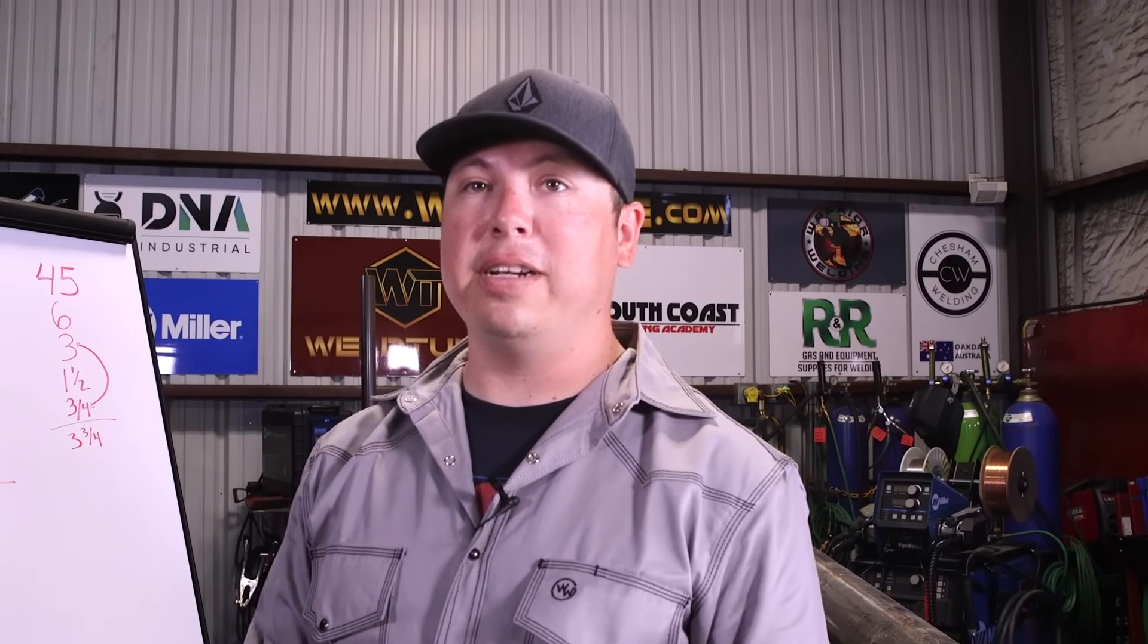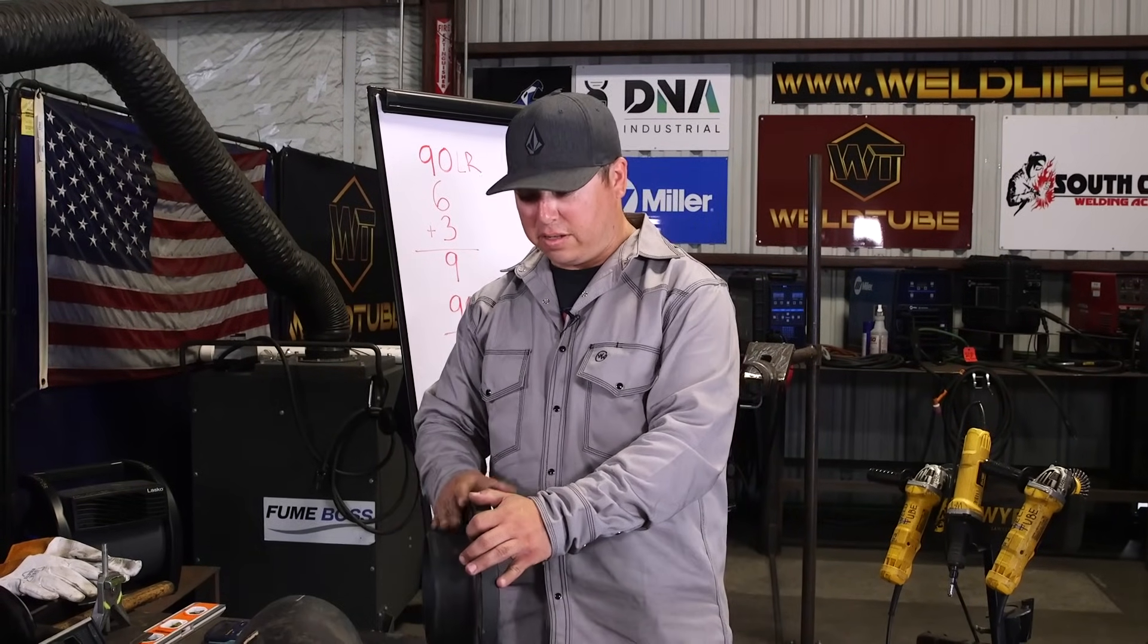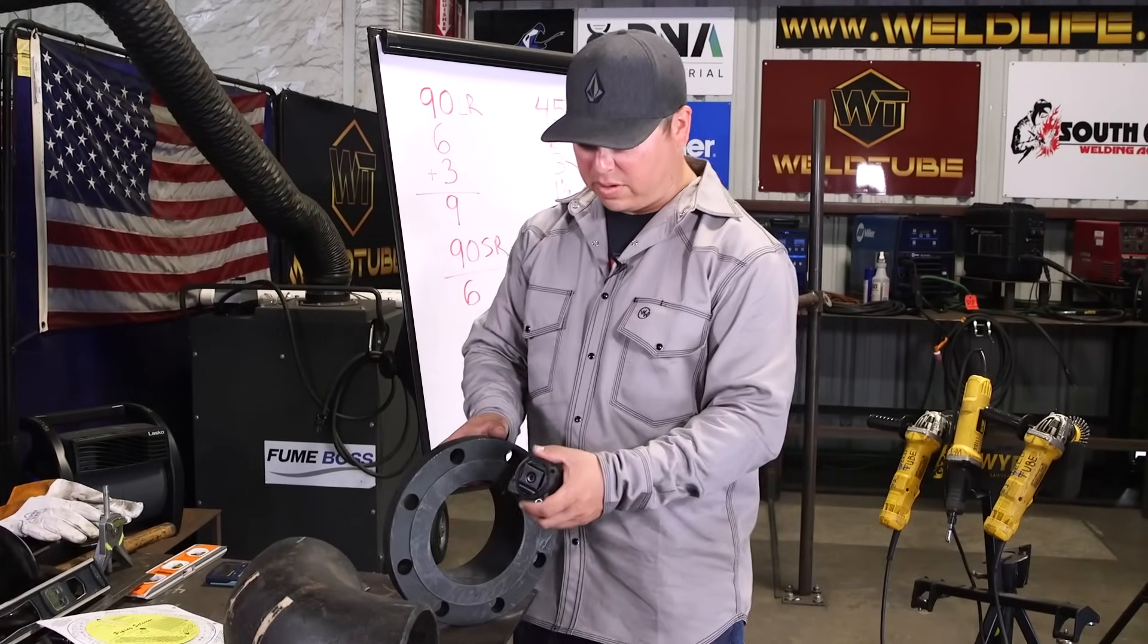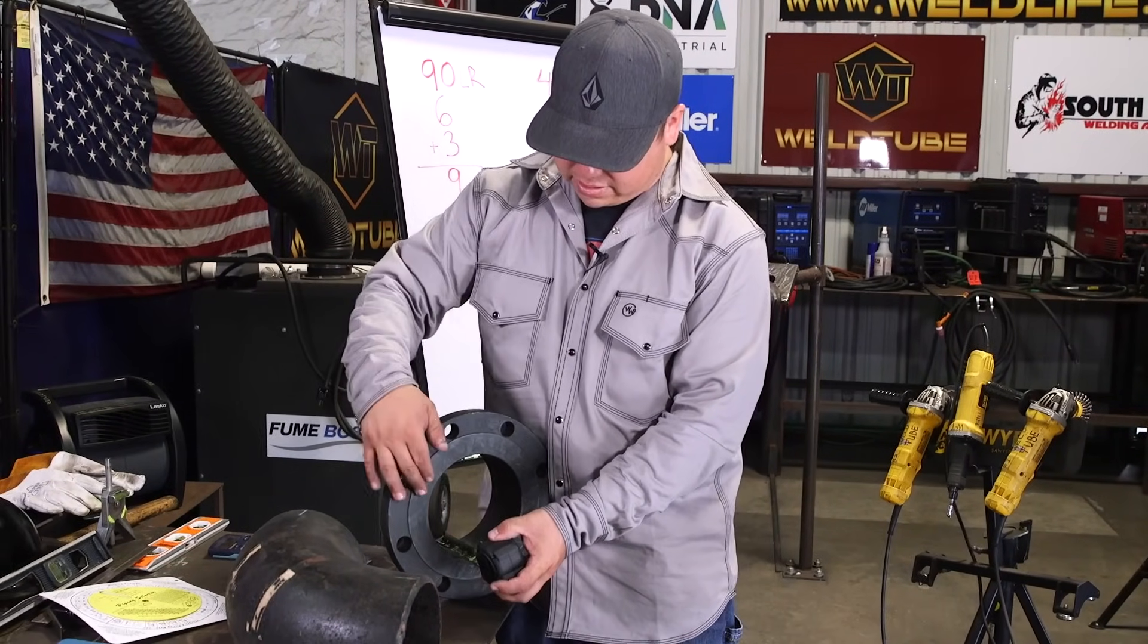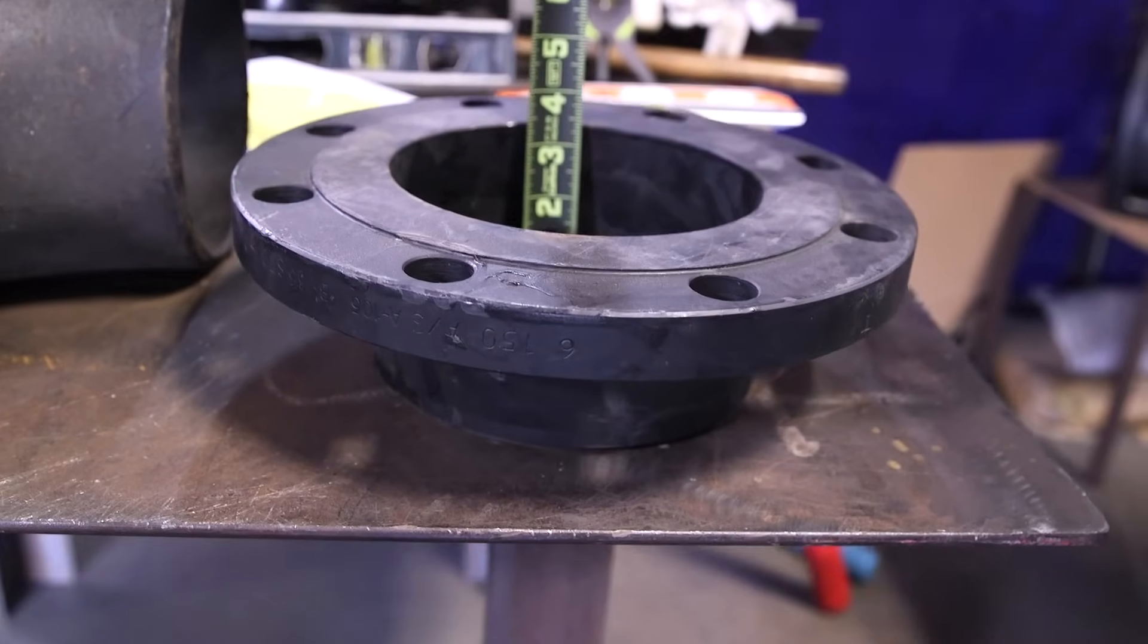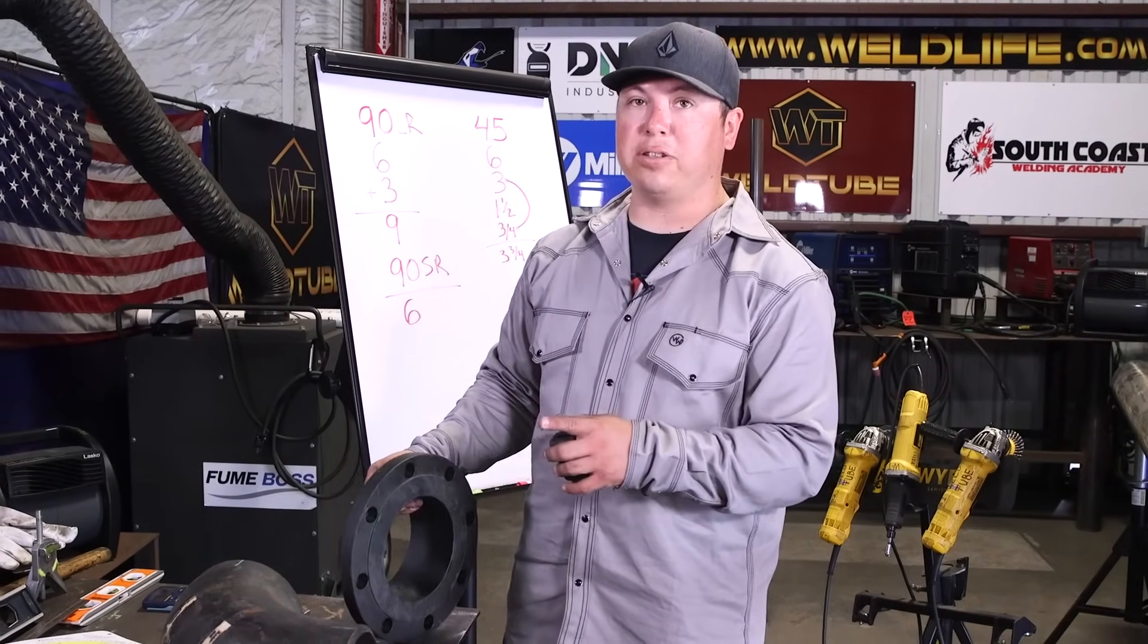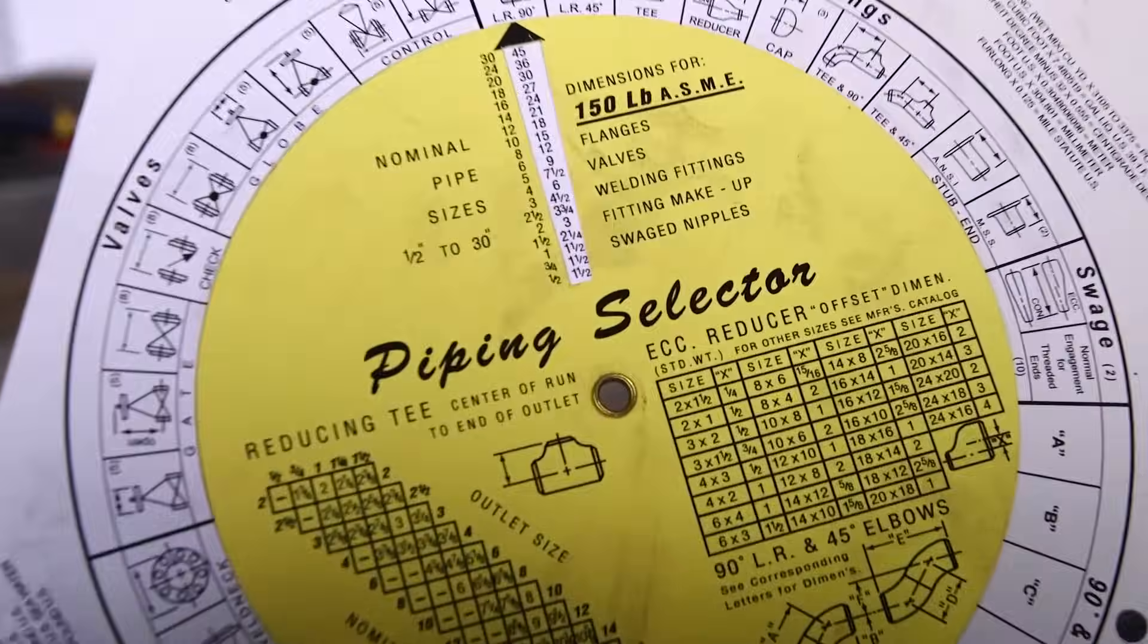Alright guys, so I'll show you guys how to get a takeoff of this flange here. The simplest and easiest thing, if you have access to the fitting already in front of you, you get your tape measure. You actually put it on the inside and measure all the way to the face of your flange here. This particular 6 inch 150 flange is 3.5 inch takeoff for it. This information can also be found on Chico cards, the piping selector wheel and your blue book as well.